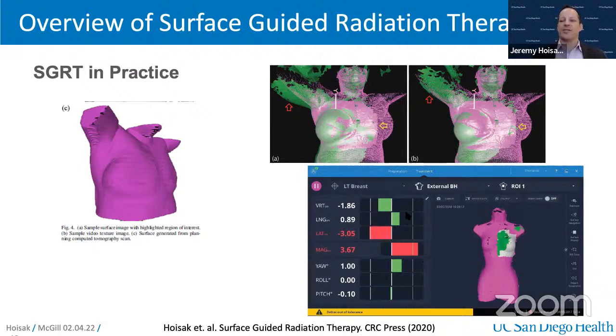And these thresholds for detecting motion, this can either be just manually configured to sort of halt a treatment beam if the patient moves, or they could be automatically gated if you have a connection between this system, SGRT system, and your linear accelerator.